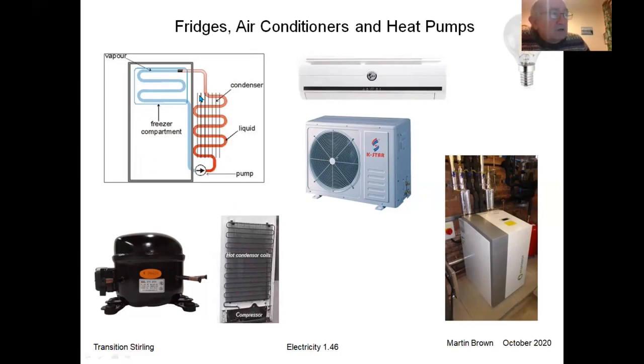The liquid they use, of course, in the past was Freon 12, which was found to be an ozone damaging chemical. That's why when you take your fridge for the tip, you mustn't put it on the tip, and you may have to pay to have it dealt with, because they have to remove the liquid very carefully from the old fridges.